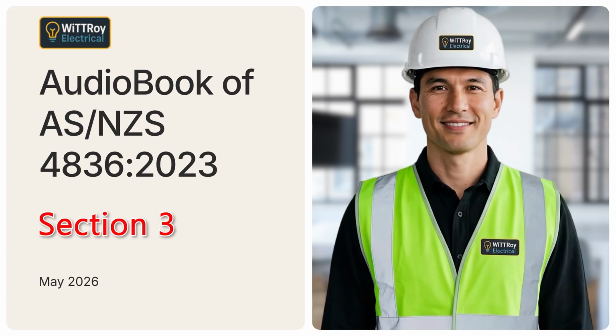If the electrical installation is complex, the isolation procedure should be checked by another competent person. Complex installations may include backup supplies, generator supplies, multiple isolation points, remote control isolators, and safety services. In simple terms, the more complex the installation is, the more careful the isolation process must be.